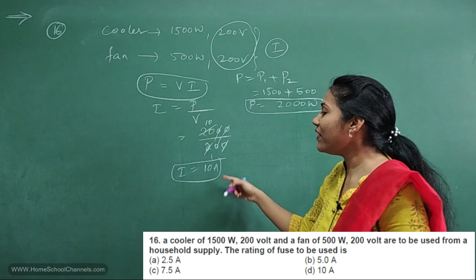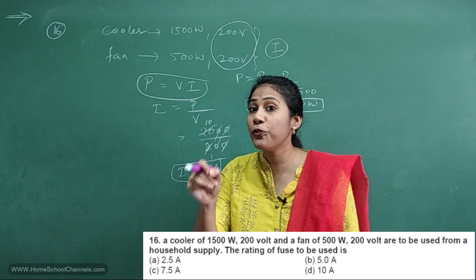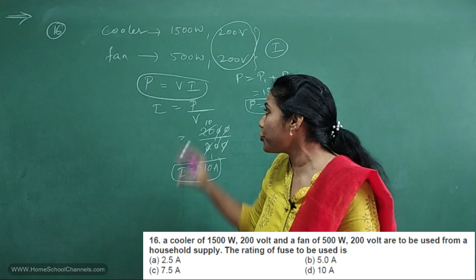But the power, add the powers here. So P is equal to P1 plus P2. P1 is the power of the cooler, that is 1500. P2 is the power of the fan, that is 500. So altogether you get 2000 watt. Total power is 2000 watt. Substituting, 2000 divided by 200 is definitely 10. So the current taken by these instruments would be 10 amperes. So a fuse with a capacity of 10 ampere or above can be used to protect these electrical appliances.